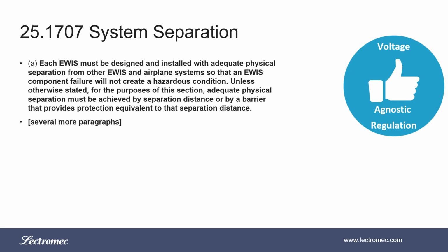25.1707 deals with system separation. Part A says that each EWIS must be designed and installed with adequate physical separation from other EWIS and airplane systems so that an EWIS component failure will not create a hazardous condition, unless otherwise stated. For the purposes of this section, adequate physical separation must be achieved by separation distance, or by a barrier that provides protection equivalent to that separation distance.